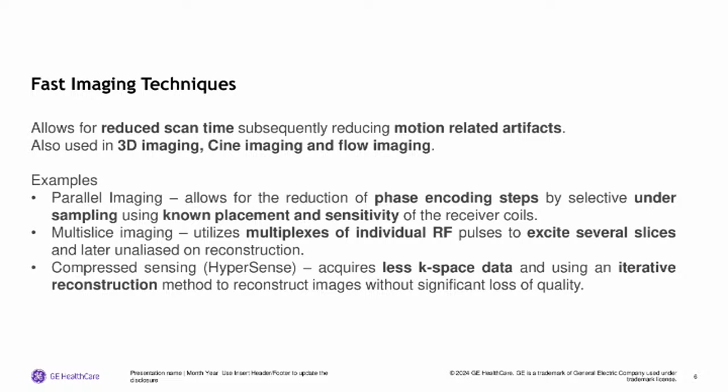So what we do in parallel imaging is that we can undersample in that specific region. The coil that is anterior, or to the front side of my head, will sample more signal on that region. Since we know the positioning of the coil, we are able to combine the images, and this will improve the image quality, and also we are able to scan faster.